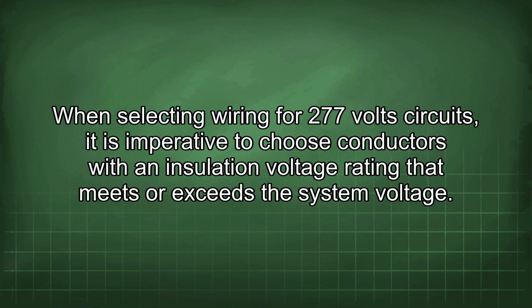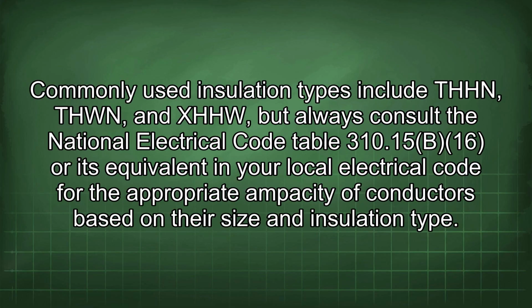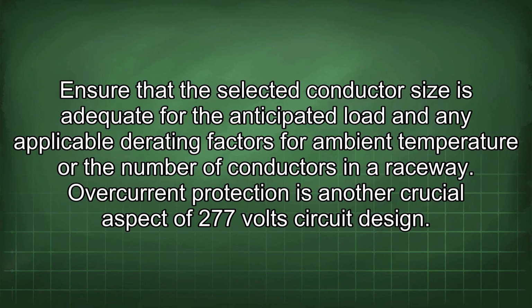installation. When selecting wiring for 277 volt circuits, it is imperative to choose conductors with an insulation voltage rating that meets or exceeds the system voltage. Commonly used insulation types include THHN, THWN, and XHHW, but always consult the National Electrical Code Table 310.15(B)(16) or its equivalent in your local electrical code for the appropriate ampacity of conductors based on their size and insulation type. Ensure that the selected conductor size is adequate for the anticipated load and any applicable derating factors for ambient temperature or the number of conductors in a raceway.